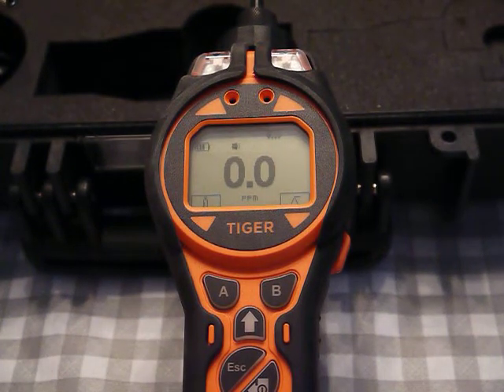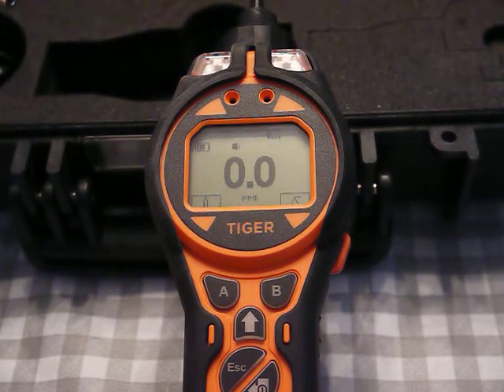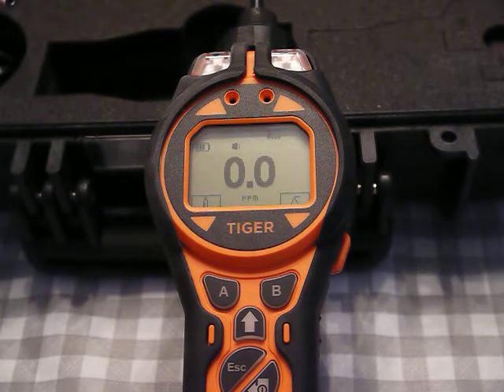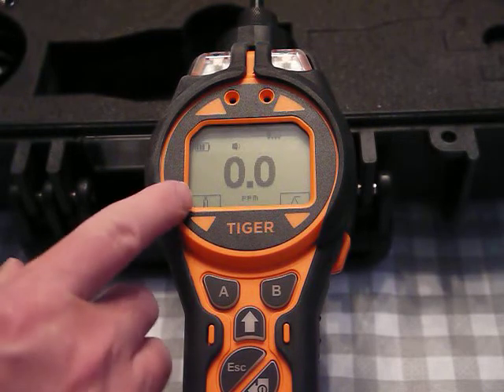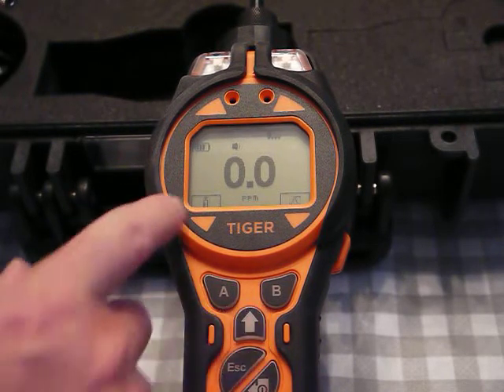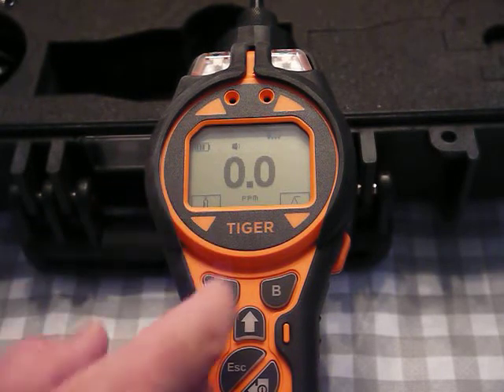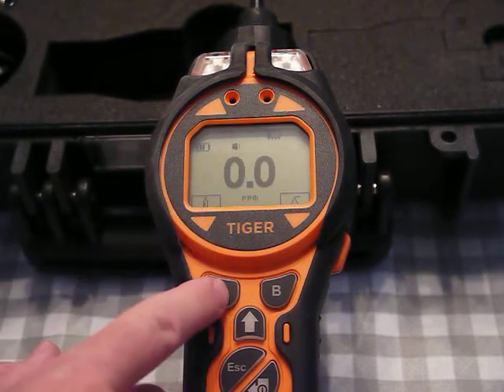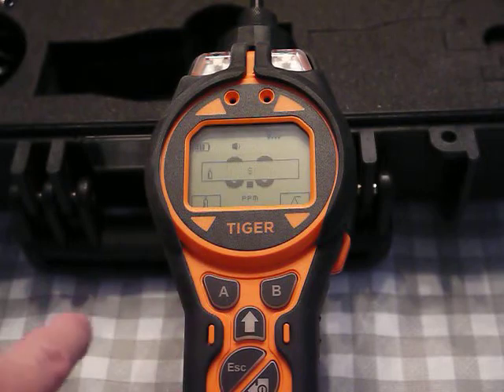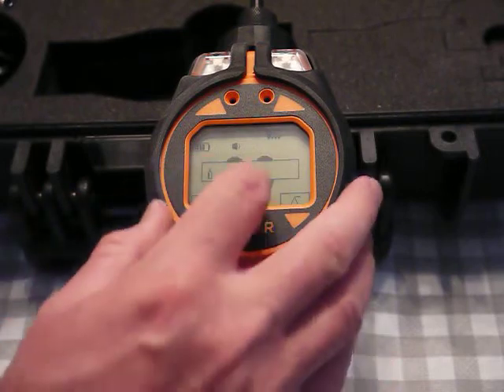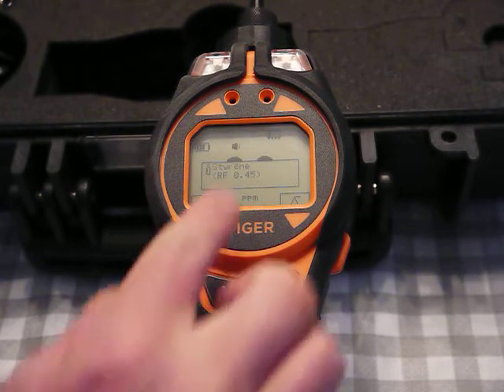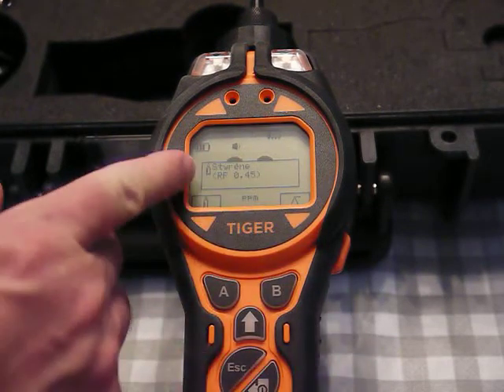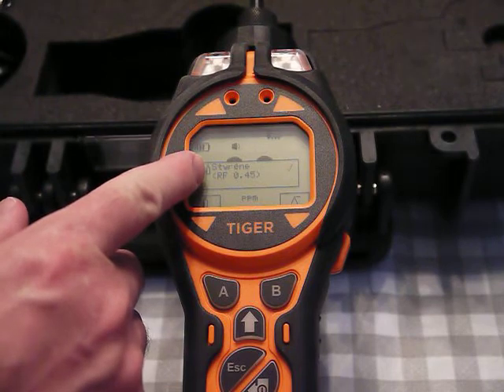In a previous video I showed how to set the Tiger to calibrate it with isobutylene, but then set it up to measure for styrene. If you just had styrene only in an area you want to measure, you'd use these up and down arrows to get to where there was a little cylinder of gas shown, hit the A button underneath that cylinder of gas, and under S you can go through the alphabet with these up and down keys. Under S we selected styrene, which has a response factor of 0.45.